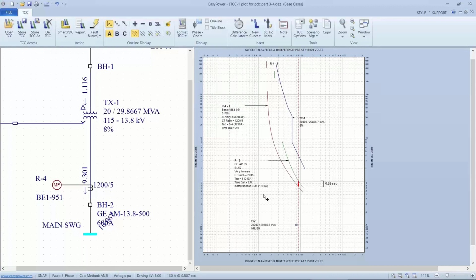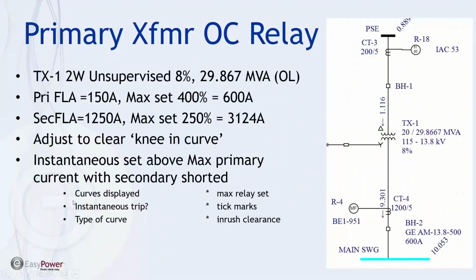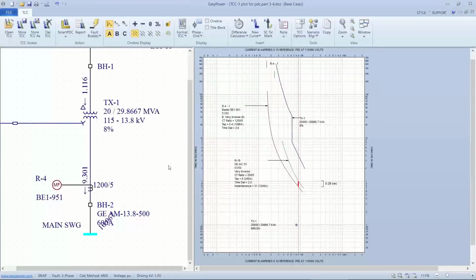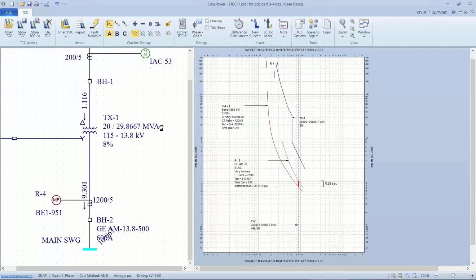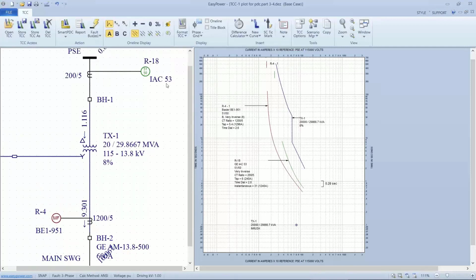Okay, so let's say I'm going to live with this. So we talked about the curves, the instantaneous trip, the type of curve. We didn't talk about the instantaneous trip. Okay, when I go back to my transformer, my primary settings, if I fault all the buses, I see that there is an instantaneous trip on R18, and it's set for somewhere around 1220 amps, which is just slightly above this 800 or 1100 max fault current.